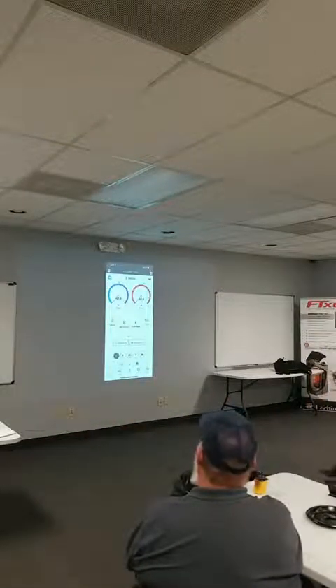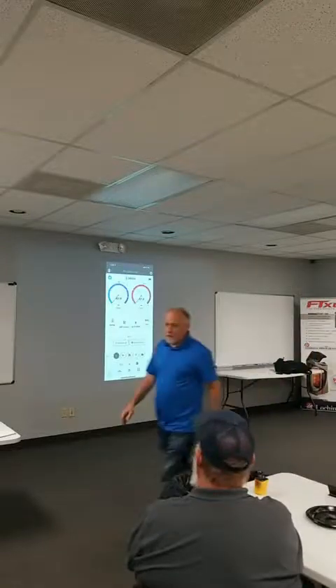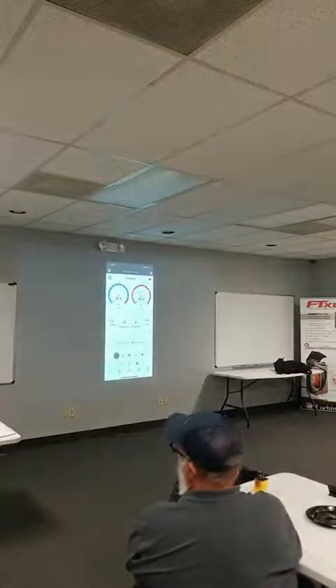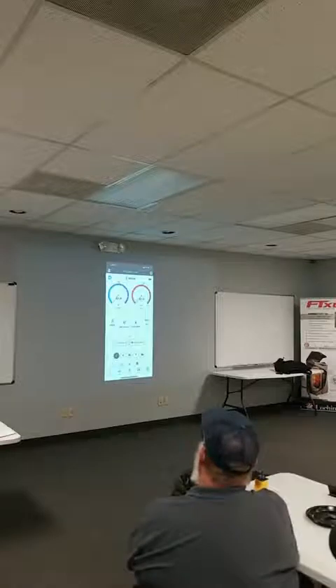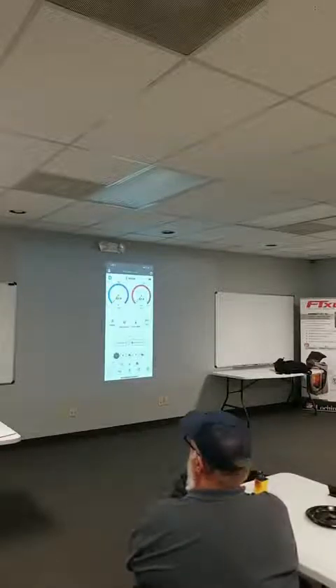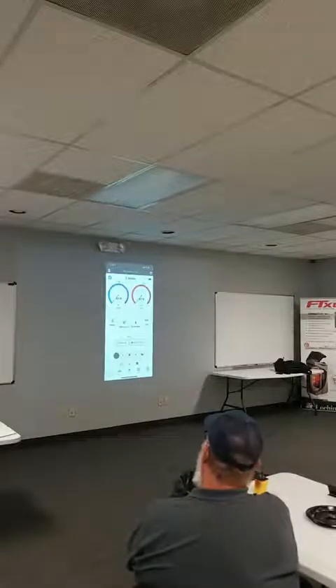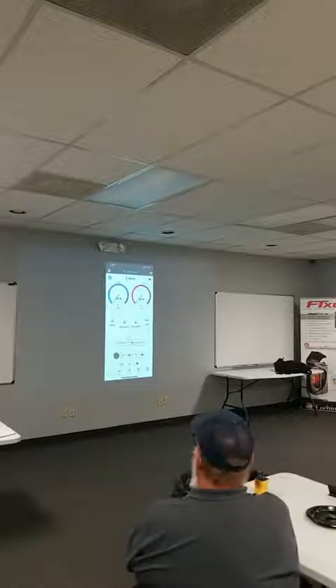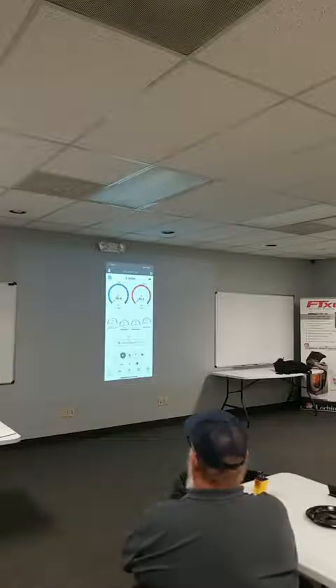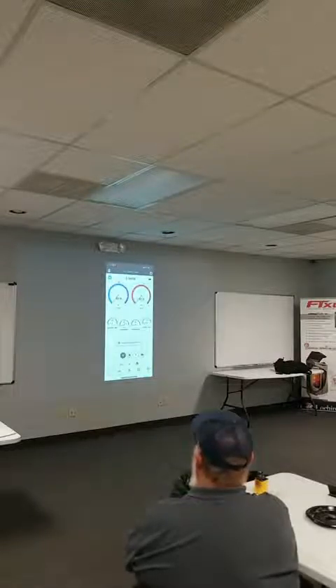All right, so you can see up there, a couple of changes we made in Measurequick. One new one is you don't have to go to your toolbox anymore to turn on your tools. As soon as you turn on your Measurequick app, it'll pick up the probes and start putting the targets up. So right now, he just turned on the return air probe and the outdoor air probe on the system, okay? And if we look here in a second, he turns them on, a suction line, superheat, subcooling on there.